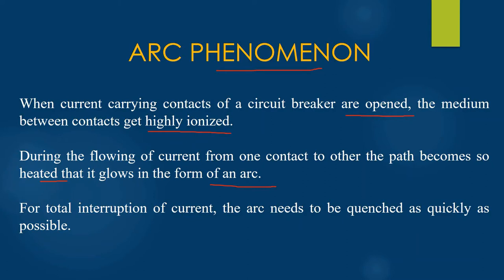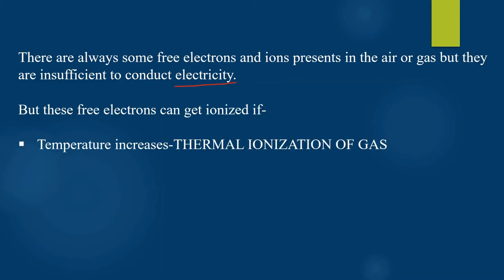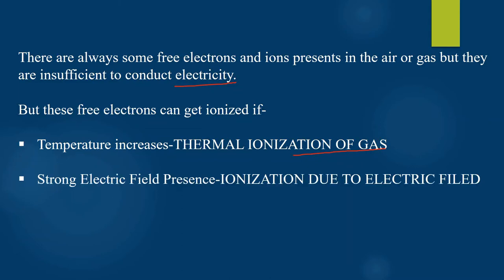For the total interruption of the current, it is mandatory that this arc so developed needs to be quenched as quickly as possible. We know that there are always some free electrons and ions present in air or gas, but they are insufficient to conduct electricity. They can conduct electricity only if the temperature increases — this is called thermal ionization of the gas. This temperature increases because the current density increases as a result of the contact area being decreased when the two contacts are separated. Also, the free electrons are able to conduct electricity in the presence of a strong electric field, which is known as ionization due to electrical field.